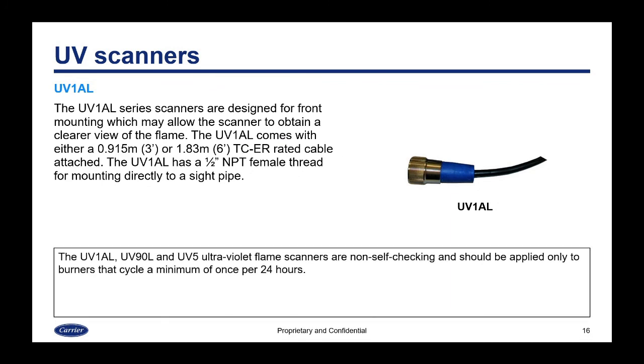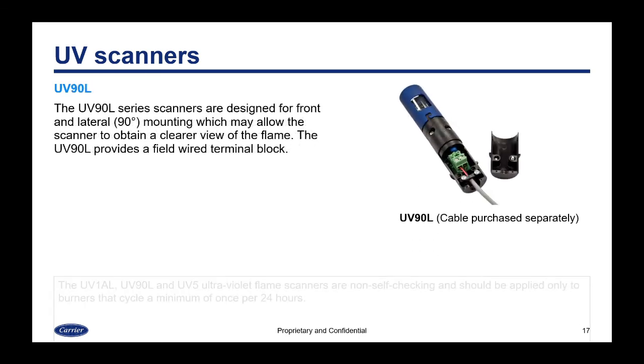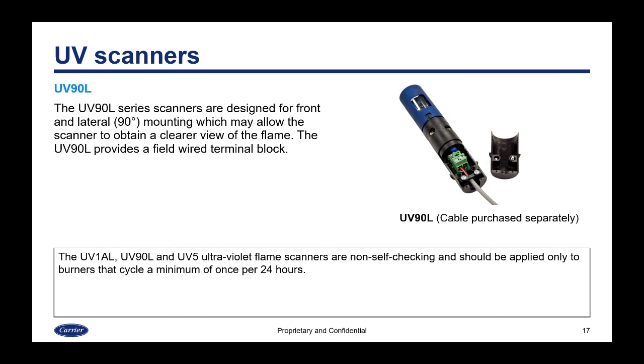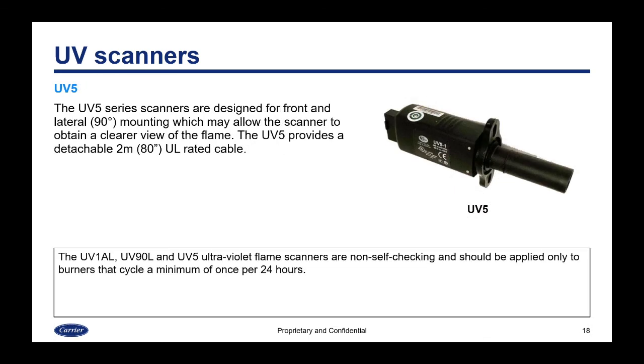The first scanner choice is the UV1AL, and this is designed for front mounting, and it allows the scanner to obtain a clear view of the flame through a sight tube. And it comes with either a 3-foot or 6-foot cable attached, and it mounts with a 1/2-inch MPT thread. The next choice is a UV90L scanner, and this is designed for front or side mounting, and it allows the scanner to be more versatile. And it provides a field-wired terminal block, so you can use your own cable. And the third choice is the UV5. This is a more compact scanner, and it comes with a detachable cable and also can provide front or 90-degree viewing of the flame.